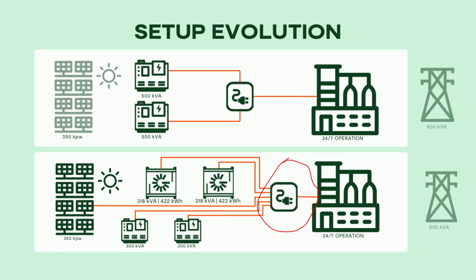And these were in a rotating scheme in fixed power, so the batteries would ask for energy from these machines when they've depleted. So you can see here, all the power assets are connected to the bus. So the 2 batteries, the 2 generators, and the solar are all connected to a common point. The generator controllers are programmed in fixed export. So when they are told to start by Greener's EMS, which can be just a simple I/O start relay, or we could control the export level over Modbus, depending on what generator controllers are being used, we can then start the generator, it will synchronize to the bus, and then the power export level can be moved over Modbus by Greener's EMS on a sliding scale, in the same way we can control the solar.